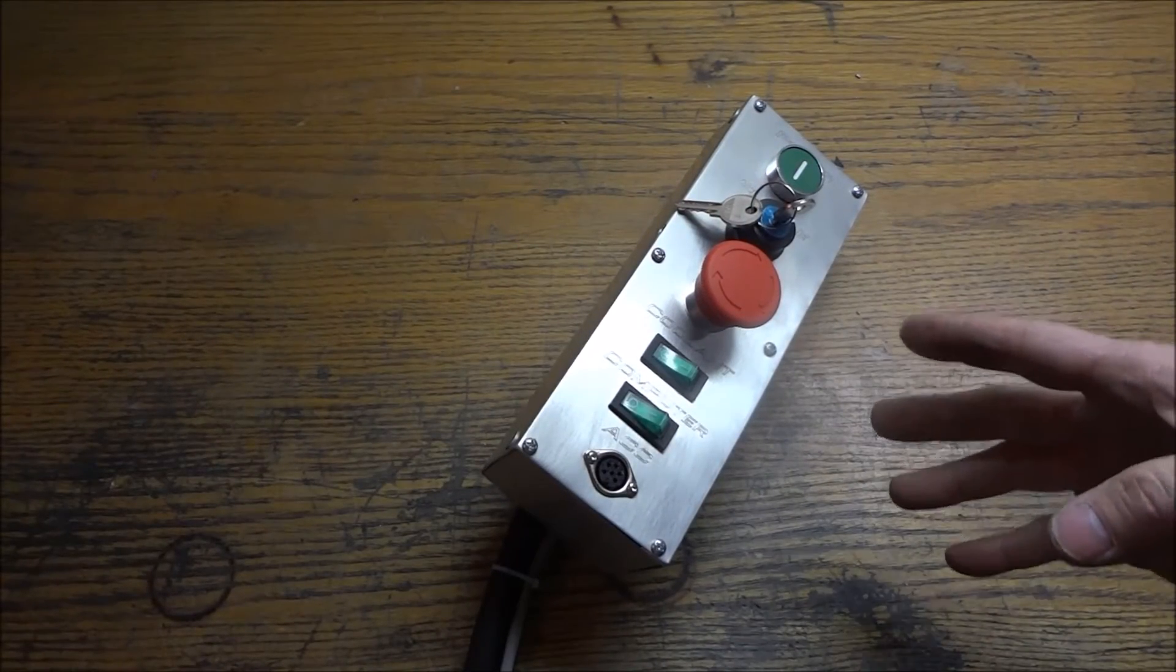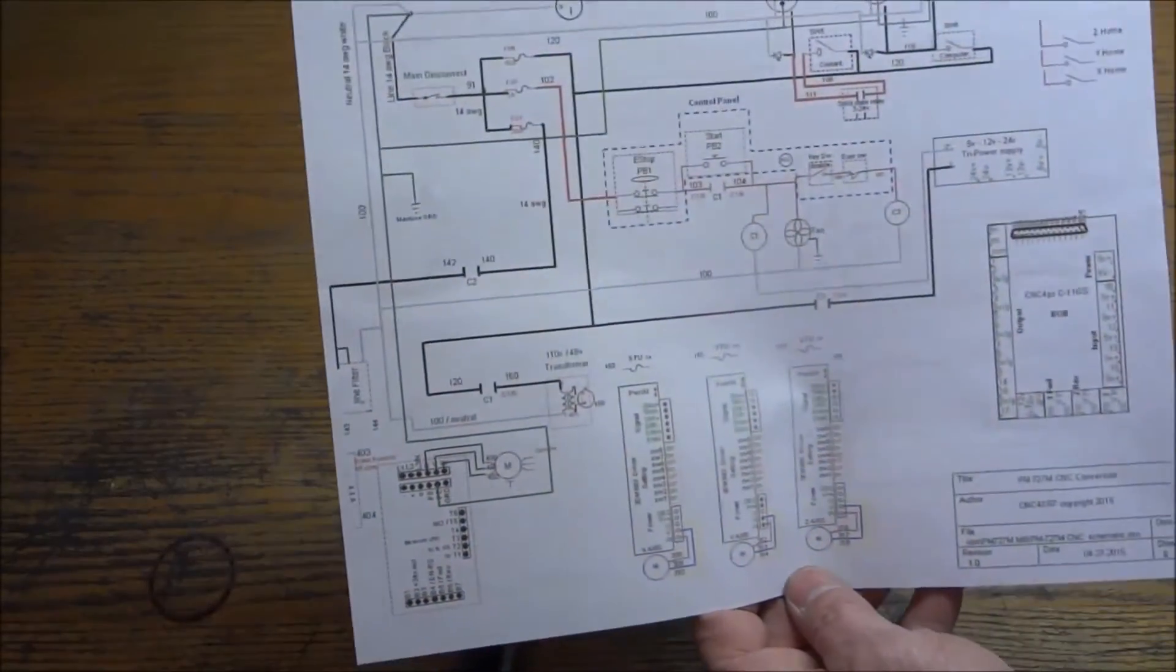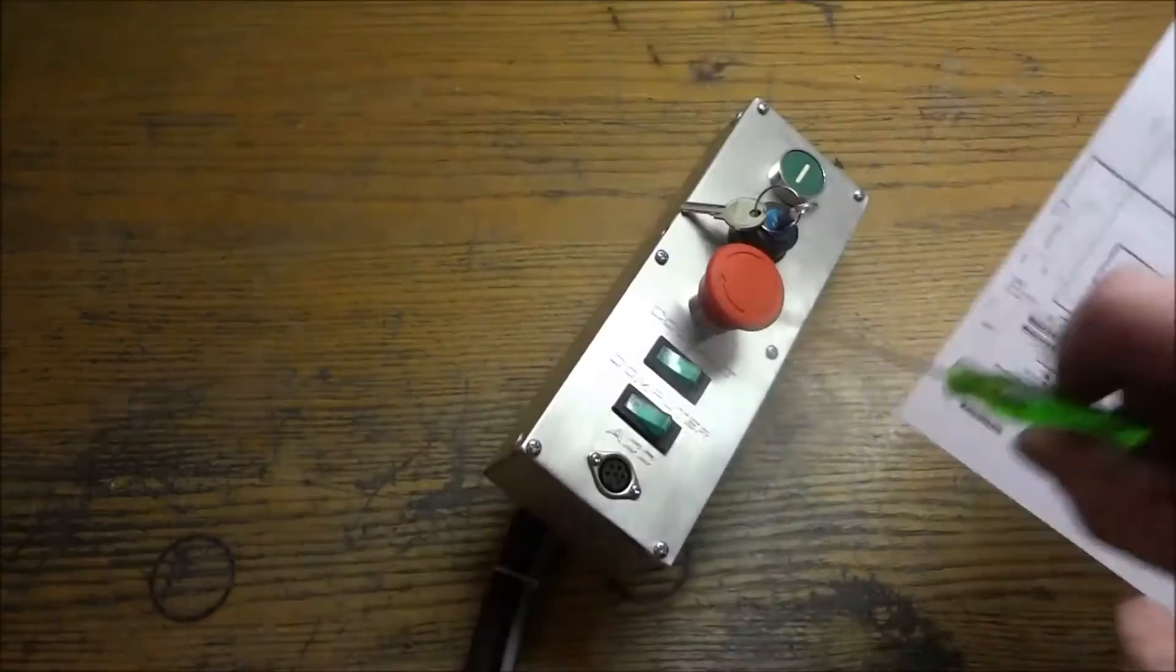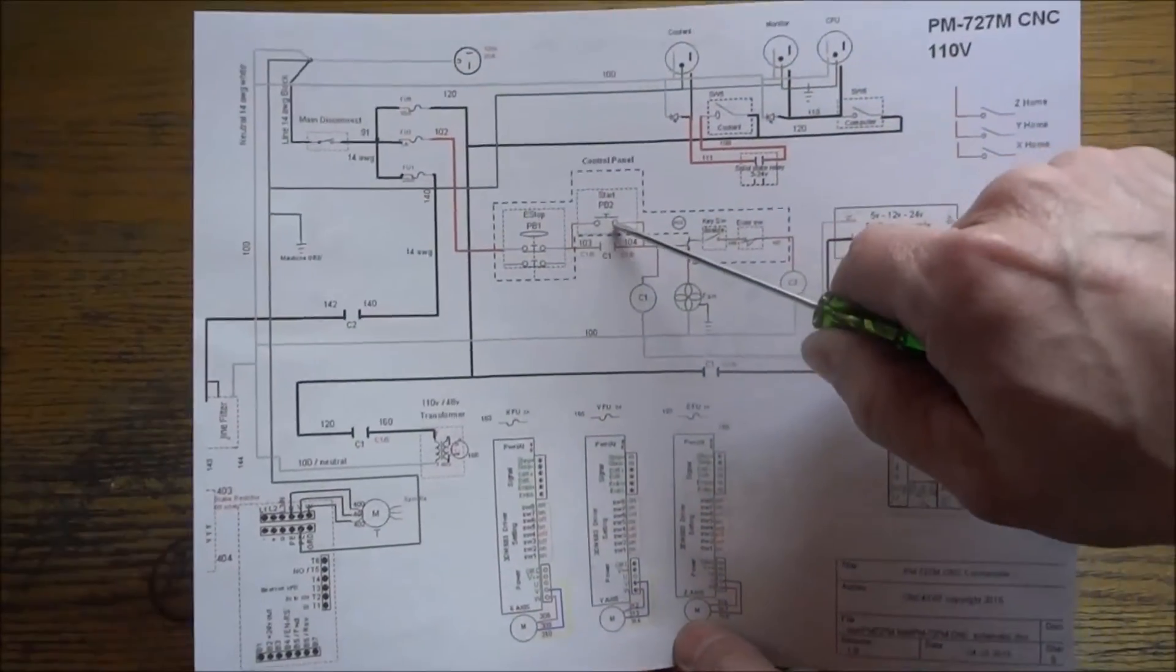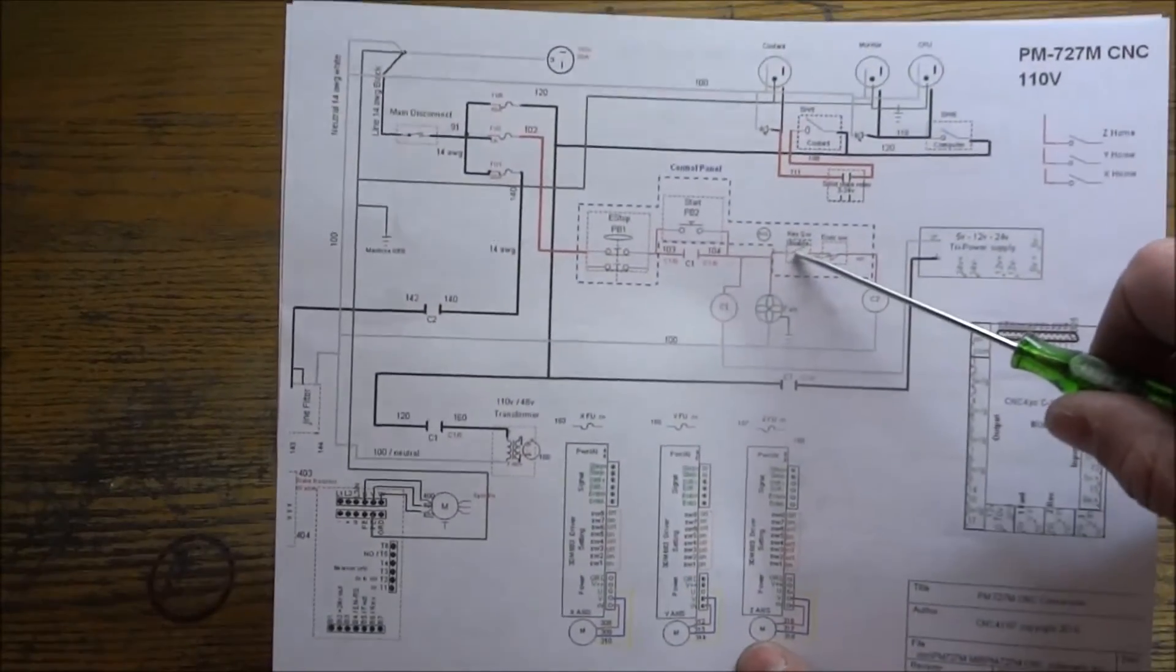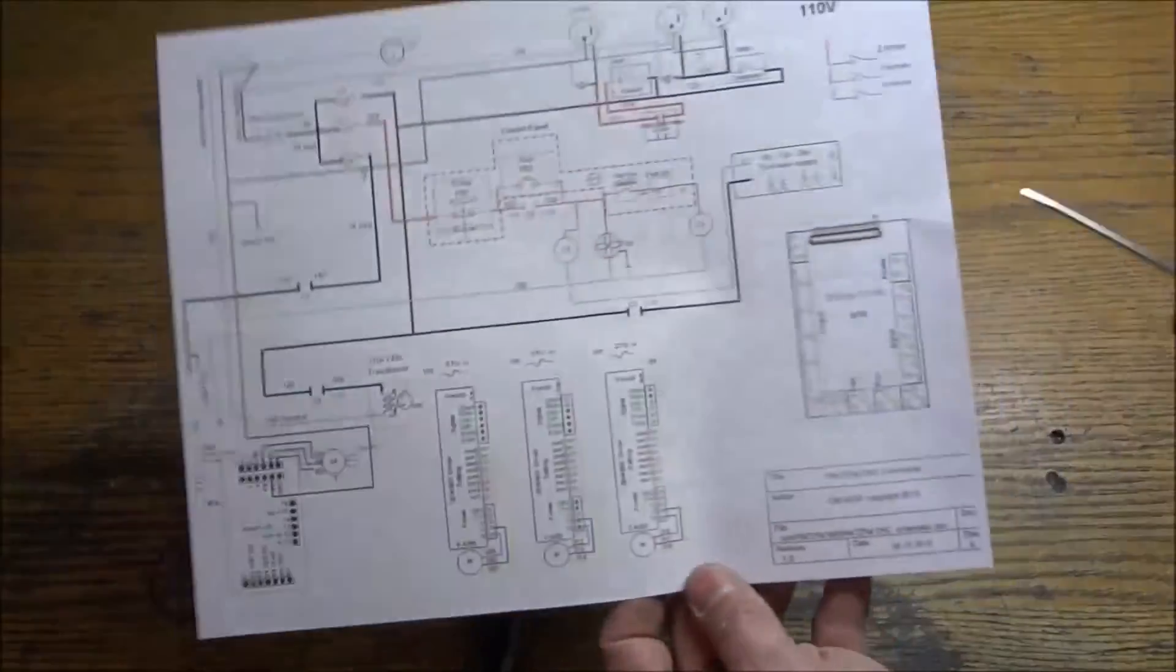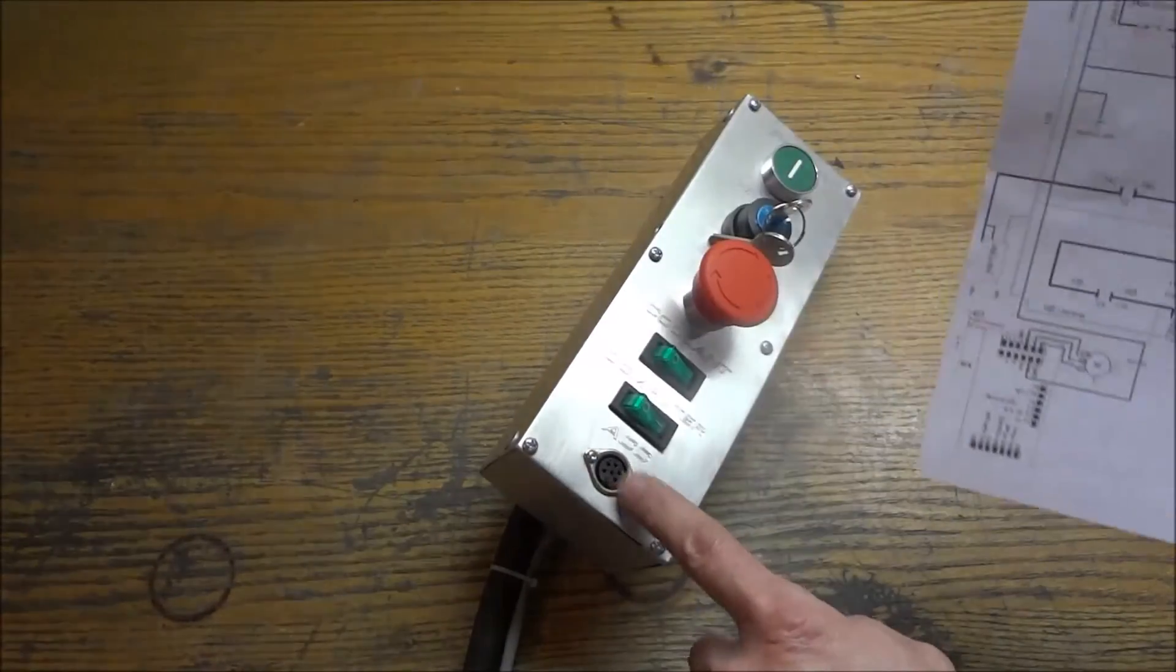Well that completes our last 110 volt circuit. That was FU3, that was a 1 amp circuit breaker for our control circuit up to our control panel. We have our power on start button, our spindle lockout key switch, we have our E-stop, our coolant on switch, and our computer on switch, and our accessory DIN connector.